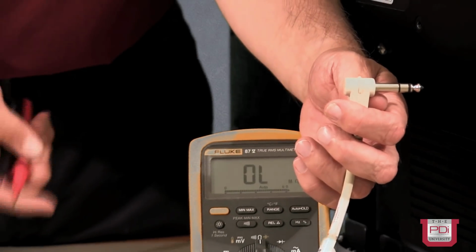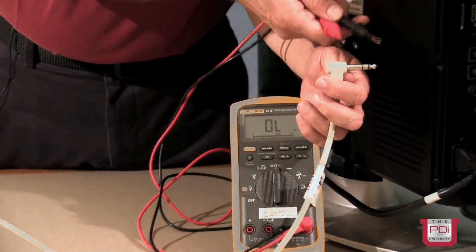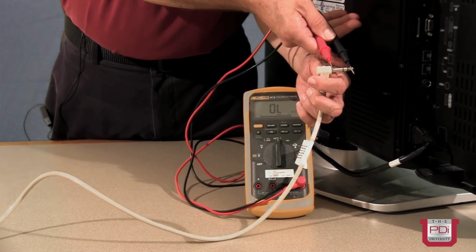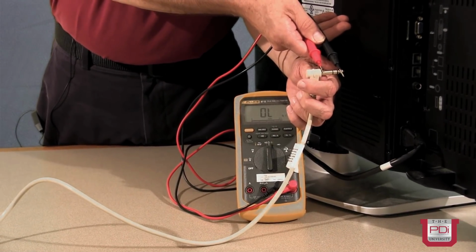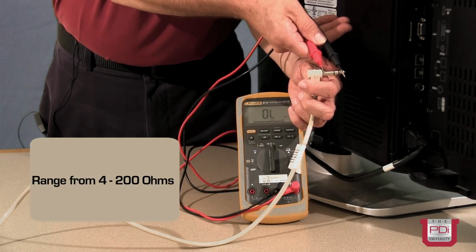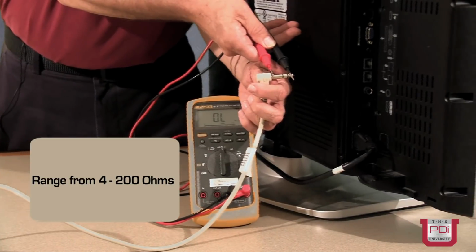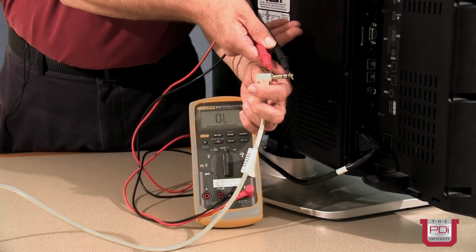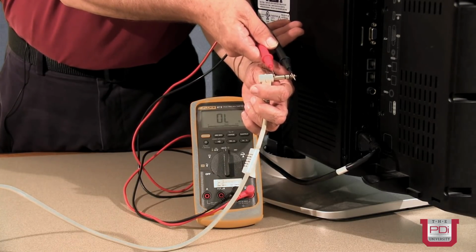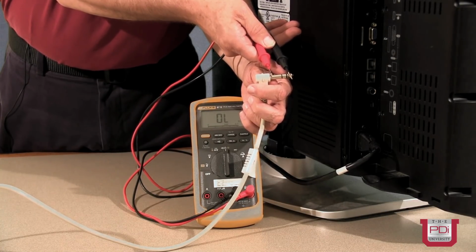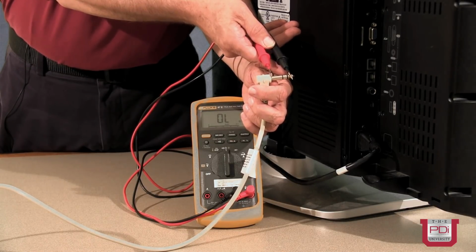So what you need to do is, with your volt-ohm meter, let's measure, just place it across the tip and the common and meter the resistance. And what you're looking for is the resistance of the attached pillow speaker's speaker, which can range anywhere from, say, 200 ohms all the way down to 4 ohms. So you're looking for that sort of resistance. If you see something that is an open circuit or a dead short, that's an indication that you've got some sort of wiring error, and you'll have to trace that out and find out where the fault is.